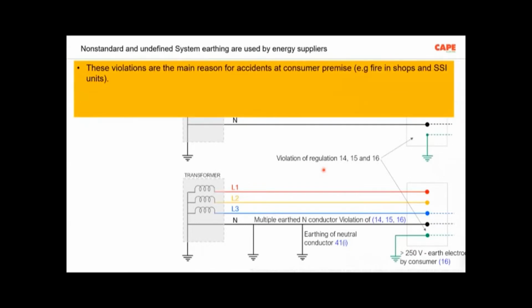Say, for example, in the hospitals, there are hospitals that have multiple low voltage supplies. I have seen a hospital a year back. They have 4 LT connections, and there are a few operation theaters in the hospital. What happens if, because of a violation by the electricity supply company, due to an earth fault, let us say, for example, in the video which we have seen, the ventilator started the fire? Your protective device will not trip.